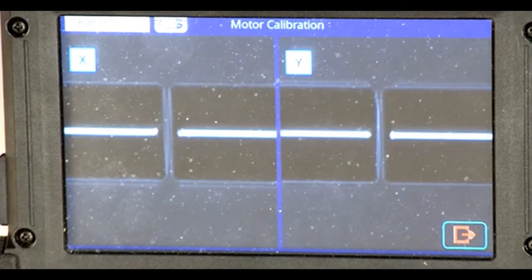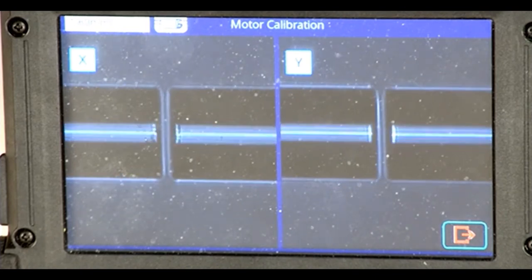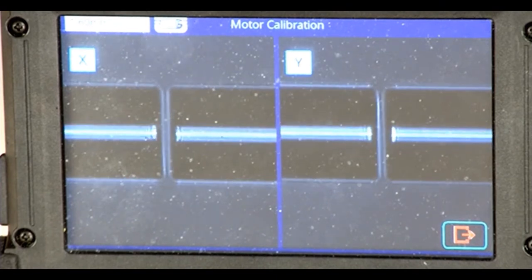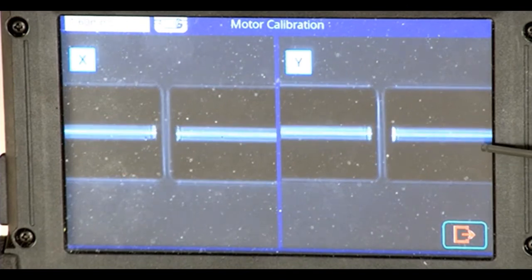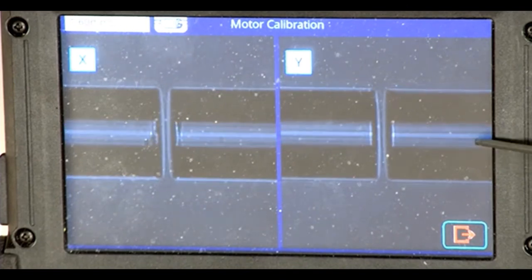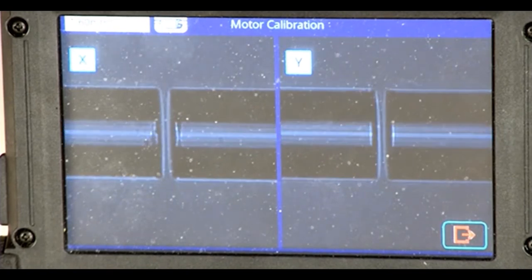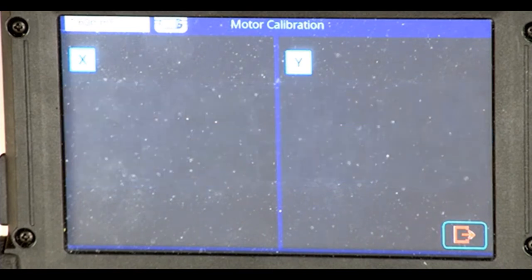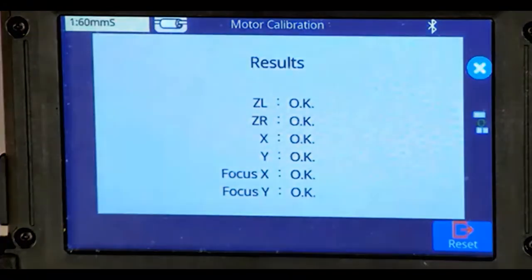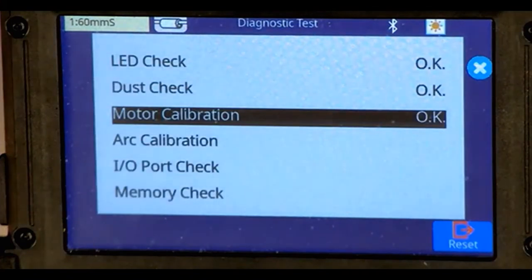And now it's calibrating the focus motion. And you notice that as it changes the focus, it's moving the camera in and out, and the bright region gets big and then it gets very small. When it's very small, you don't see that peak in there anymore. And that's one reason we have to have a high resolution optical system and focus control, because otherwise we can't pick up that peak from the core.